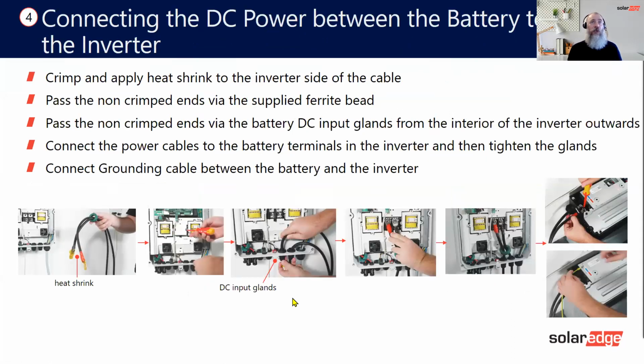Then we've got the installation of the actual battery cables. What we recommend, because you have to put heat shrink over the lugs, the ends here, is you cut the cable to the right length, you strip the cable, you put the lug on, you put the heat shrink on, you then put the ferrite coil on, and then when you've done that, you pass the cable through the inverter. So not into the inverter, but through and out. It's a lot easier that way than having to pull them up, crimp them, put the heat shrink on, and then try and mount them here.